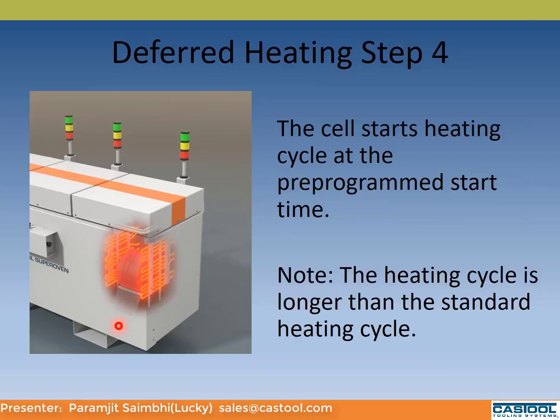We don't recommend using the deferred heating cycle if your off time is less than 6 hours, then there's no point. Another thing is if the cavity temperature is already higher, let's say it's already at 860 Fahrenheit, the cycle is not going to start. We're taking the air temperature of the cavity and saying this is the temperature of the die. If the cavity temperature is already too high, the cycle does not execute. It will just turn on the cell and go into soaking.